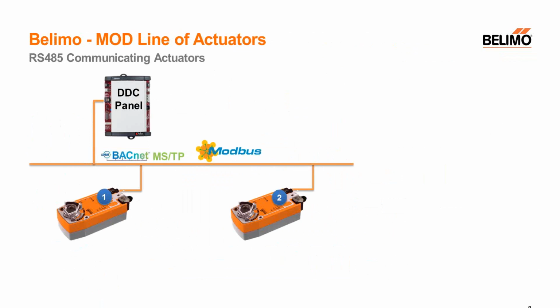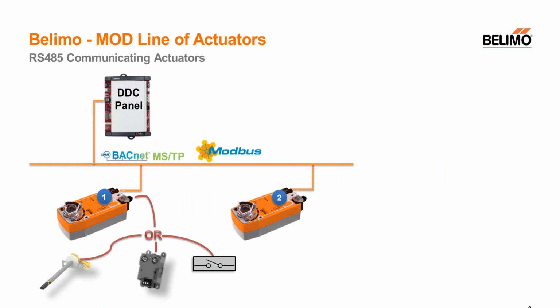So the first product I want to talk to you about, and then we'll talk about how this applies to that example, is our Dash Mod line of actuators. These are actuators that look and feel just like a standard actuator, like an SR if you're familiar with our product line, but they also include a 2-wire connection for communications, and that can be configured as either BACnet MSTP or Modbus RTU. So once you give each of these actuators an address, your DDC system can now talk to the actuators instead of using analog signals.